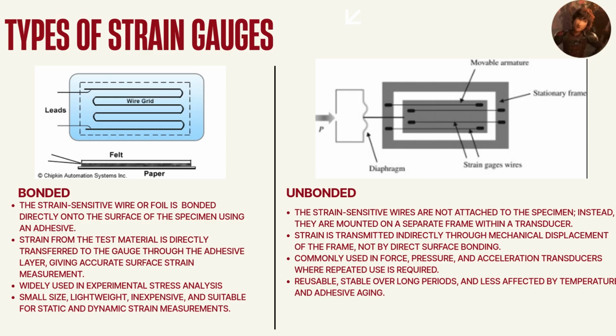As you can see in the slide, there are many differences between these two types. For the bonded type, the strain sensitive wire or foil is bonded directly onto the surface of the specimen using a special adhesive. The strain from the test material is then directly transferred to the gauge through the adhesive layer, giving accurate surface strain measurement. So in what circumstances are bonded strain gauges favored?